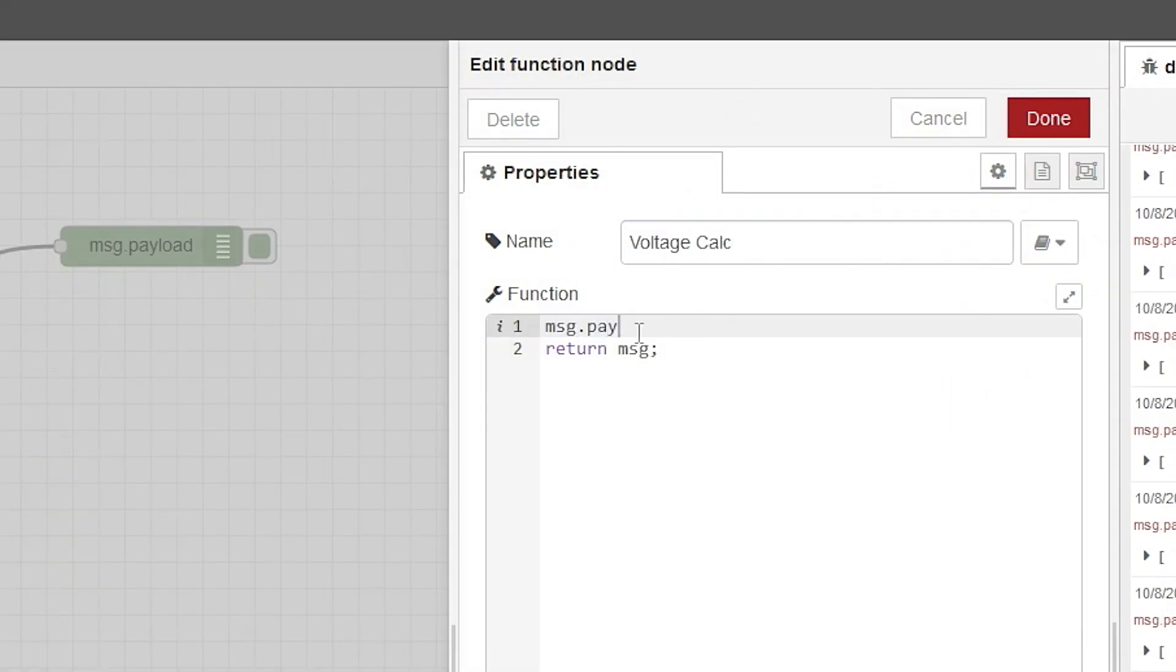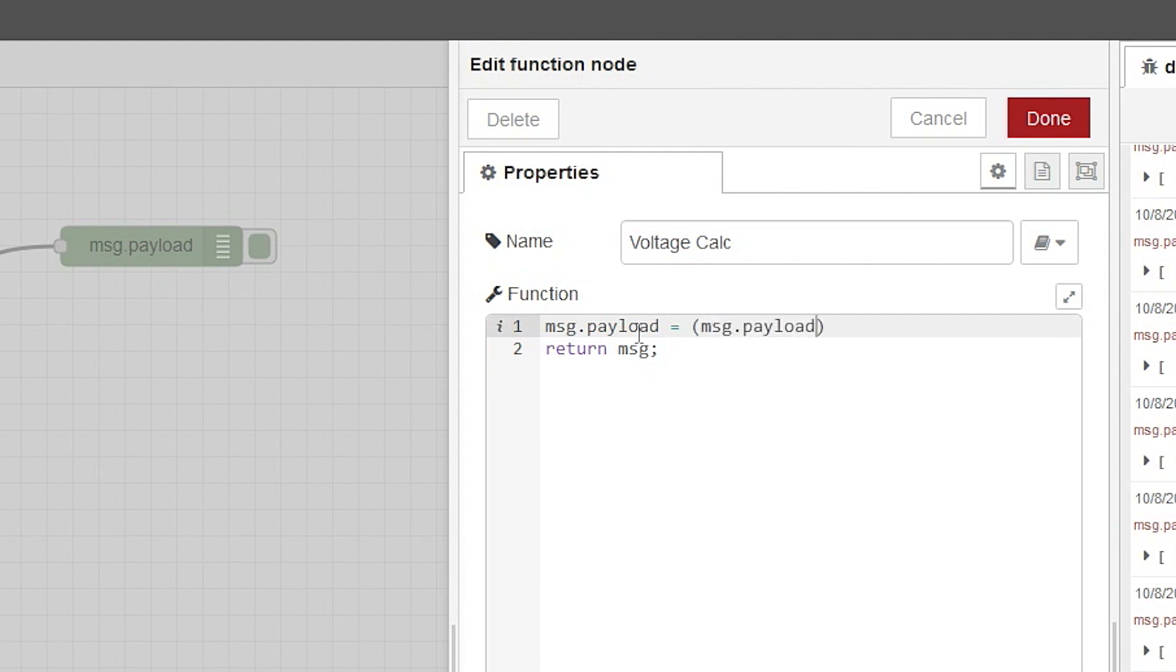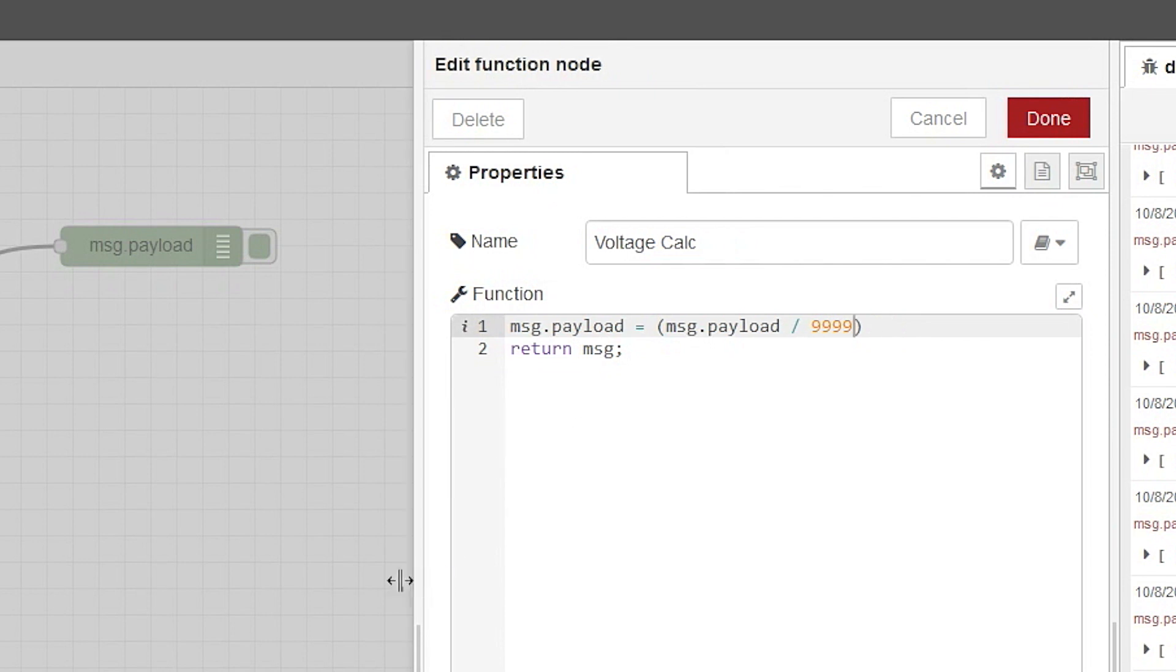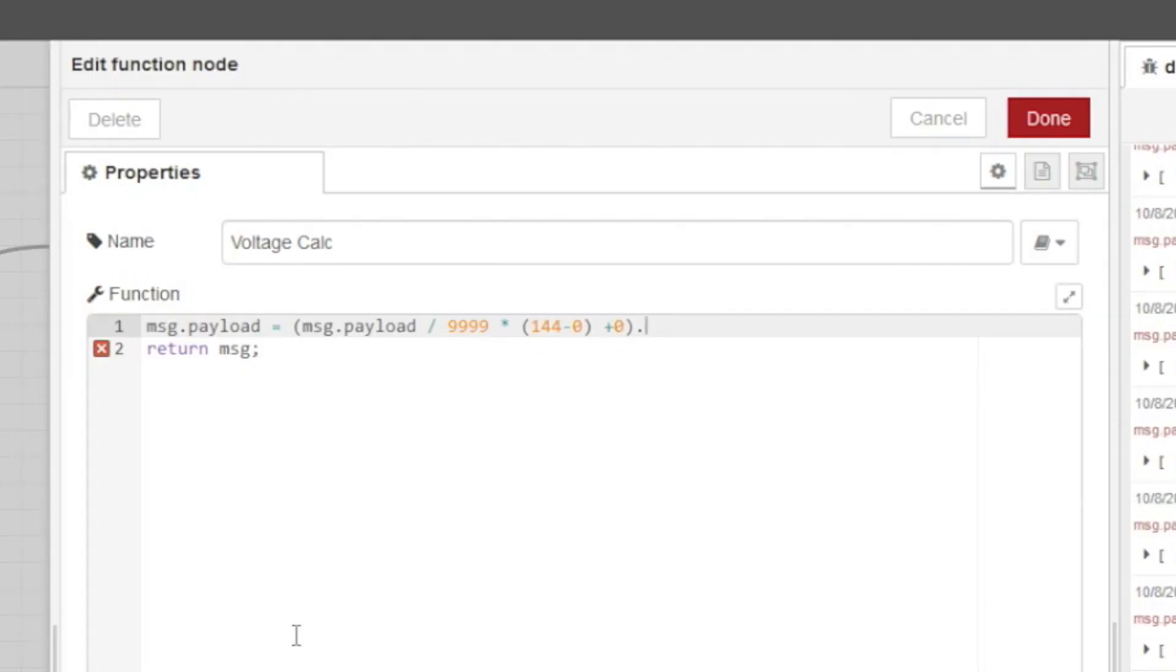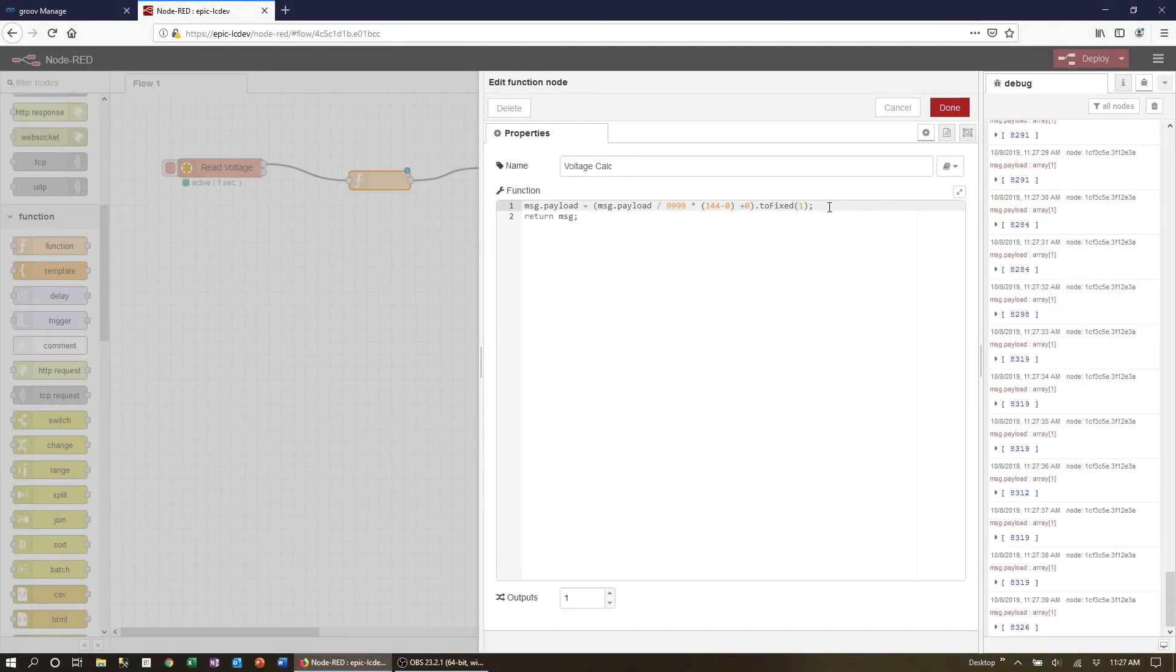We can now enter the equation: message payload equals message payload divided by 9999 times 144 minus 0 plus 0 to fixed 1. So we've simply entered the exact formula from the Modbus device manual and then fixed the result to one decimal place.